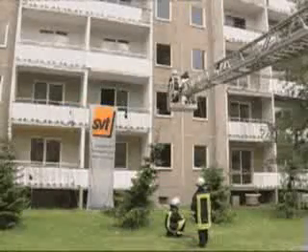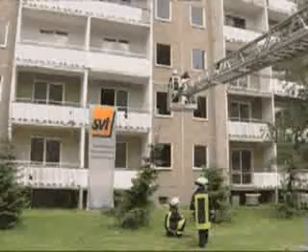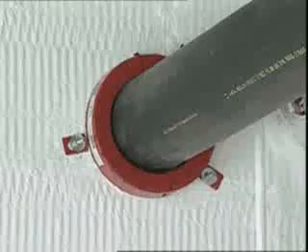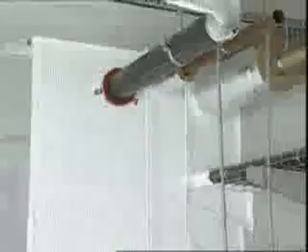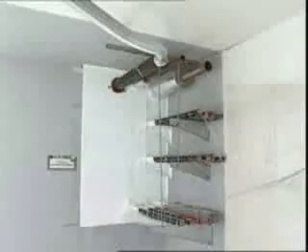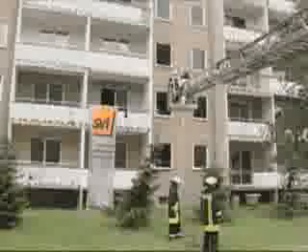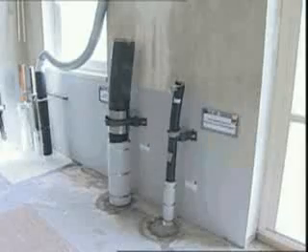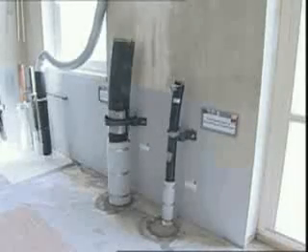Well, let's have a look at the neighboring apartments that are wall-to-wall with the test room. Here next door and at the back side of the test room, the horizontal pipes and cables are protruding from the wall. This part of the wall is protected with the PYRO-SAFE Universal Bulkhead Combi S90. In this apartment on the 3rd floor, directly above the test room, cables and pipes are protruding from the floor. These are also protected by the PYRO-SAFE Universal Bulkhead Combi S90.